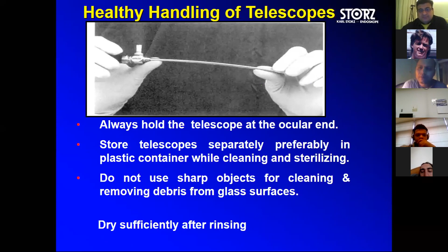Now, how to handle the endoscope, which is the main topic. Many times surgeons are using smaller diameter scopes, especially in neuroendoscopy, skull base. You are using 2 millimeter, 3 mm and 4 millimeter diameter. It is not good for the paramedical staff to hold the endoscope at the shaft and give it to the surgeon. It should always be held at the ocular lens, or one should always put on a bakelite protection white color tube, which we supply, or if it is not supplied, you can always order and buy it. It is always safe to use that, and use the containers.